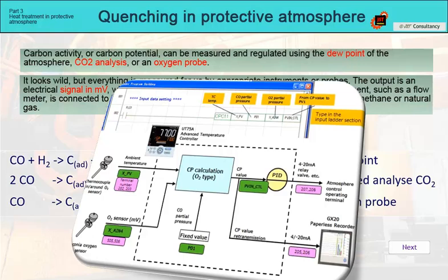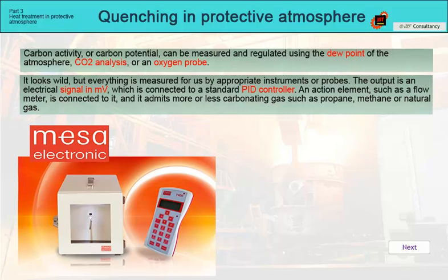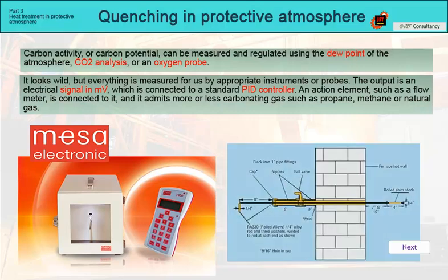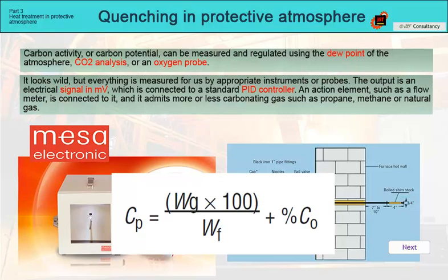However, we cannot forget the classic method of measuring CP using a test foil. Even though it is the most accurate method, with an accuracy of carbon determination of 0.01%, its use is intended rather for verifying the accuracy of other devices. The principle of the method is that a precisely weighed foil, with a defined carbon content, usually 0.1%, is placed in a heated and saturated furnace. After saturation, the foil is weighed again and the carbon content is calculated.